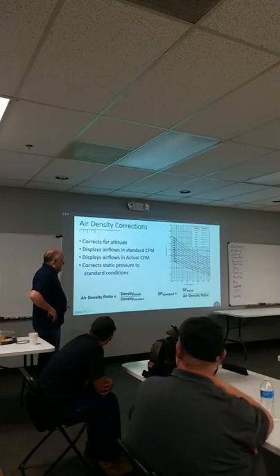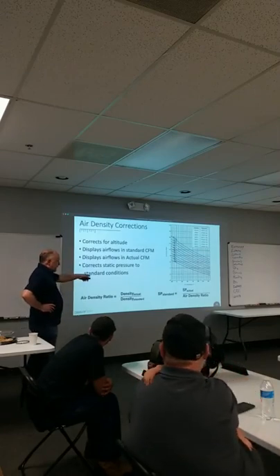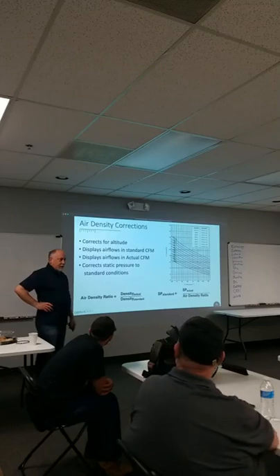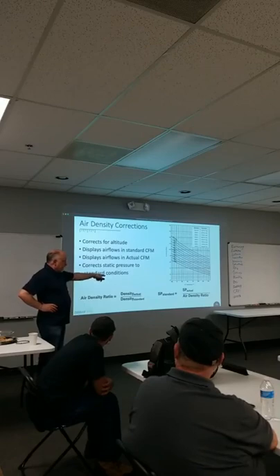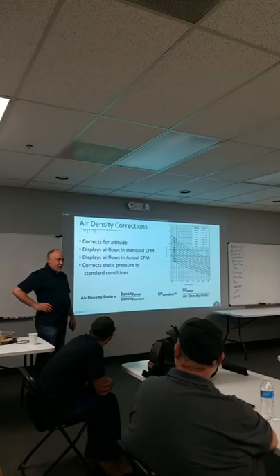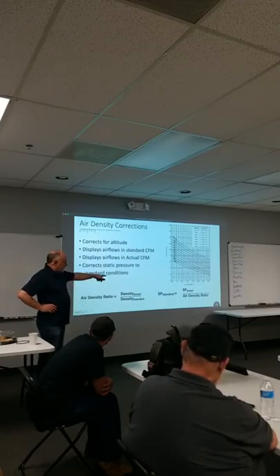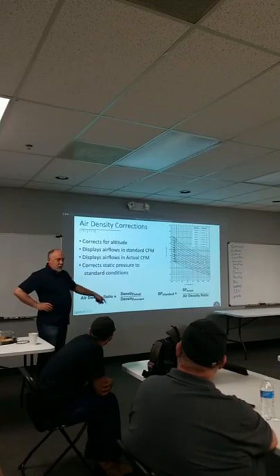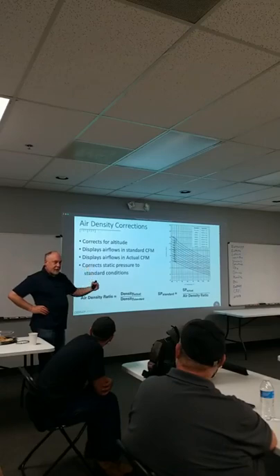Then you got your air density corrections. This is always interesting when you're looking at your standard, when you're looking at your IOM, installation operation manual. Do you ever stop and think that your static pressure is based on sea level? You're gonna have a different static pressure at elevation, at any elevation, than you would at sea level. And again, we make the corrections for that. So when you benchmark a system with Measurequick, if it's a hot, humid day, we recalculate what your static pressure is going to be at 50% relative humidity and 75 degrees Fahrenheit.